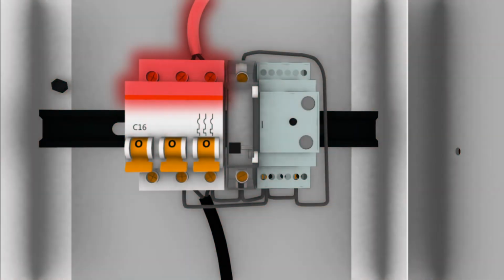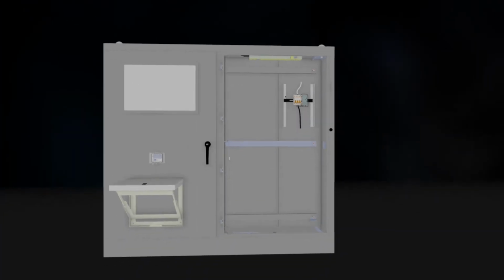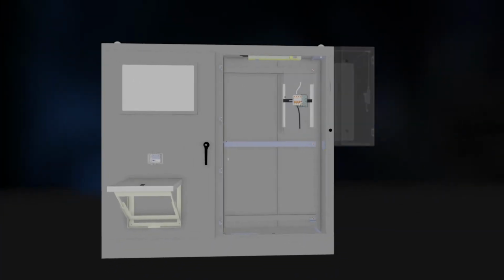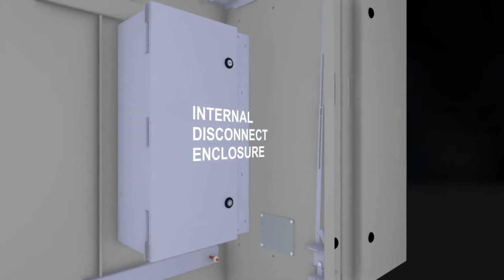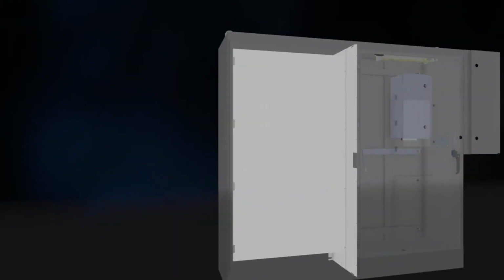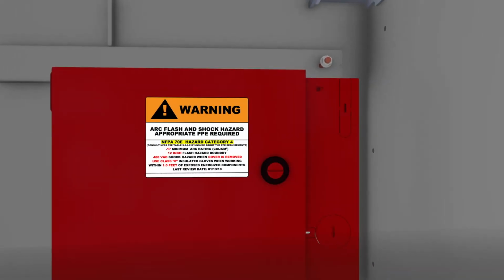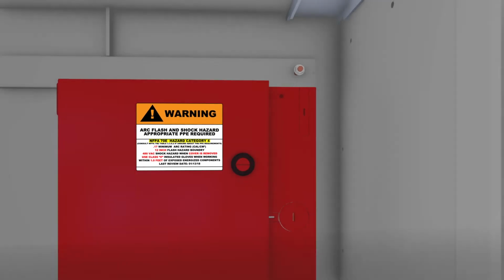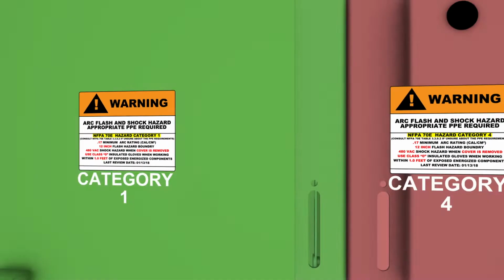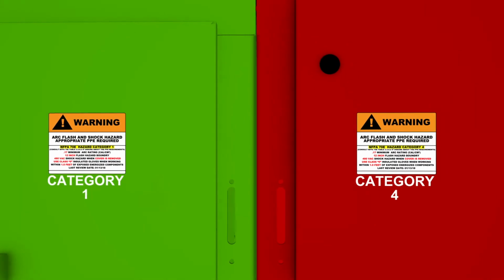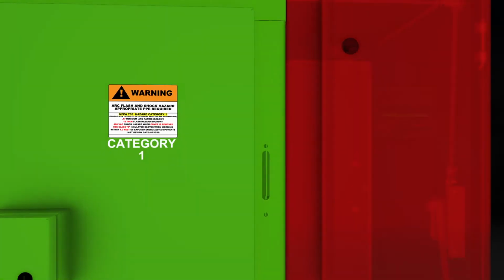in industrial enclosures. When the disconnect or circuit breaker is turned off and proper lockout-tagout procedures are followed, there is still live power to the top lugs of the disconnect or circuit breaker unless power is shut down further upstream. This is where Saginaw Control and Engineering can help by using our internal disconnect enclosure, external disconnect, or a barrier. These devices all accomplish the same basic things. They provide the barrier needed to segregate the arc flash hazard risk and require only that compartment to have a high-level PPE warning label, while the rest of the enclosure may be set to a lower PPE warning label.